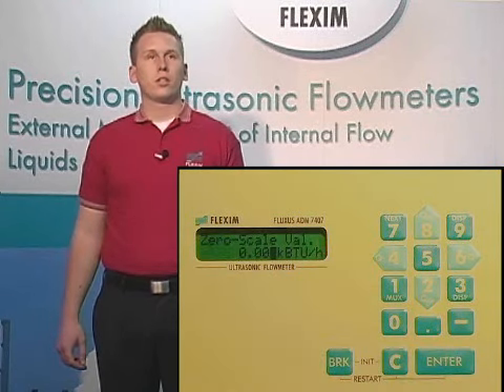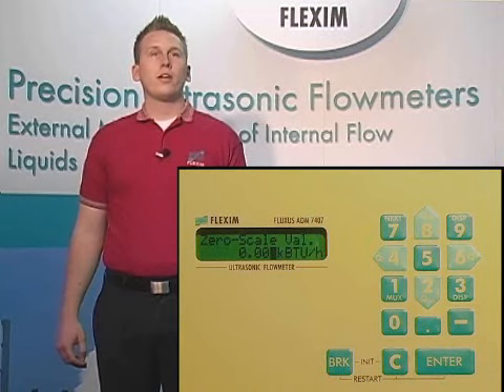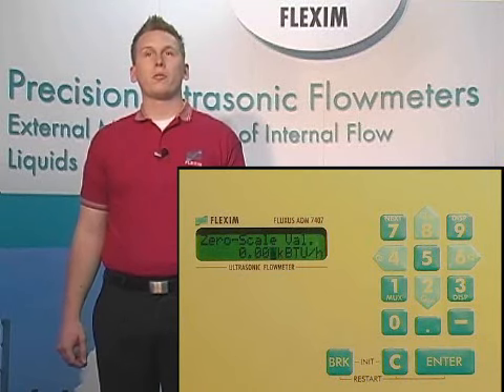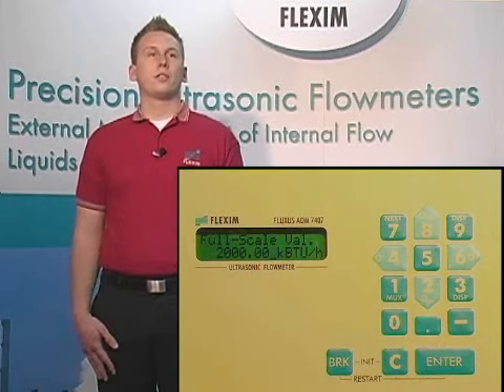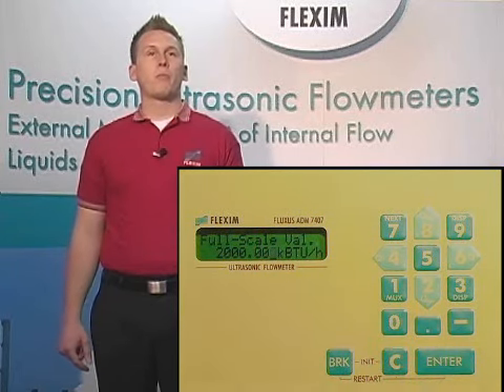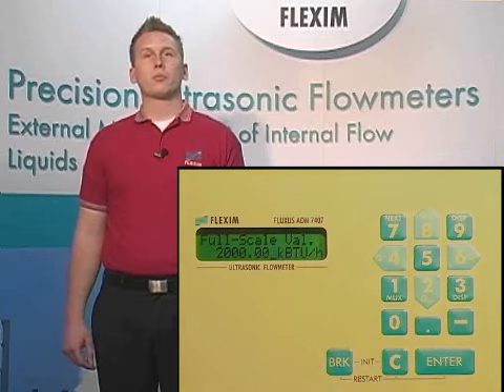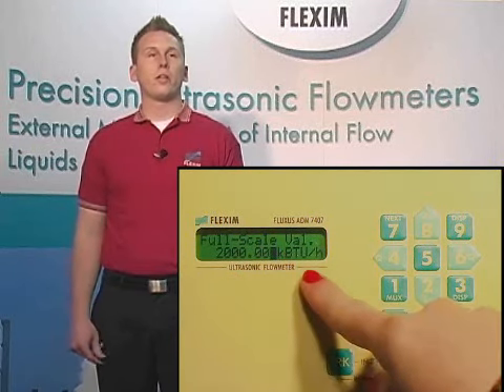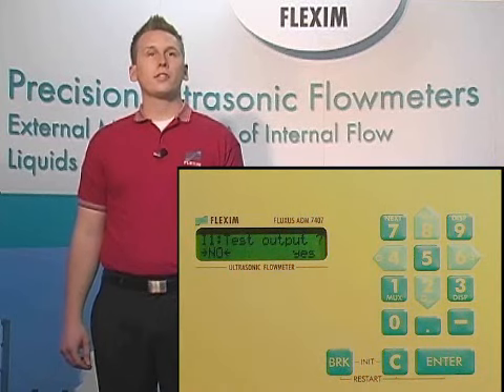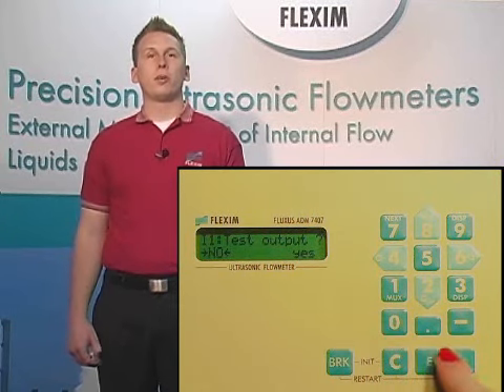Depending on how you'd like to span your 4 to 20, we could put in our lowest expected flow rate, usually 0, and hit enter. And here we can put in our max expected flow rate, plus probably about 20 to 25% headroom, so we know we won't max out our readings. And the last two options we have are to test our output. I'm going to choose no for now.